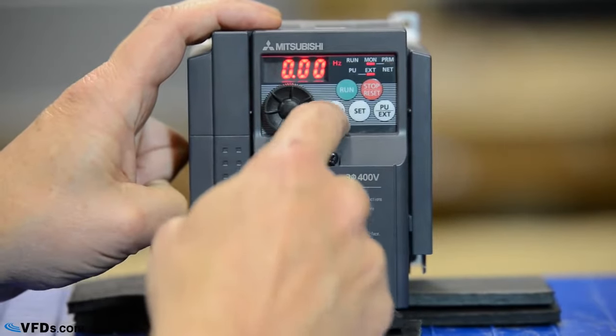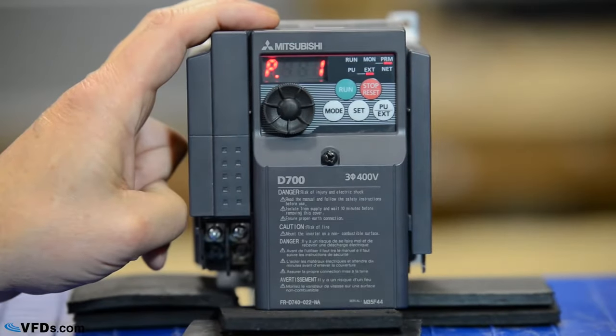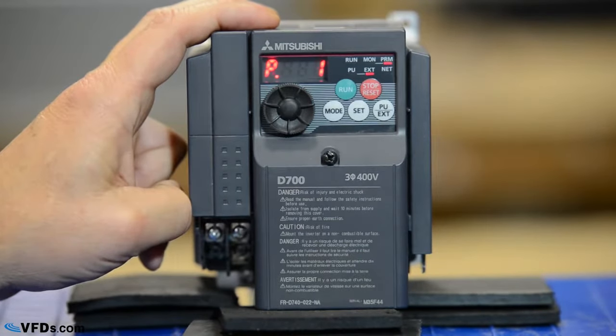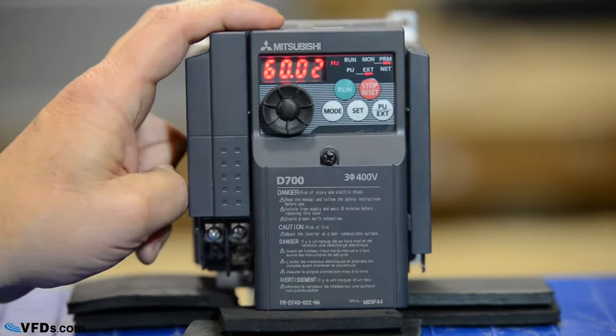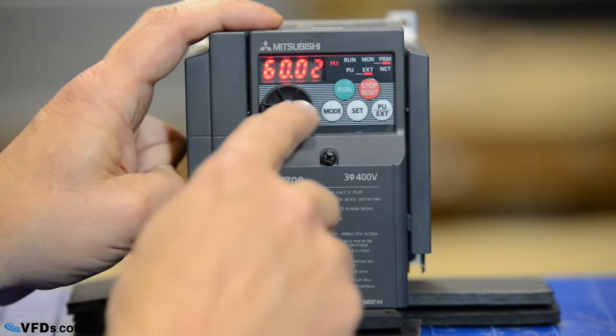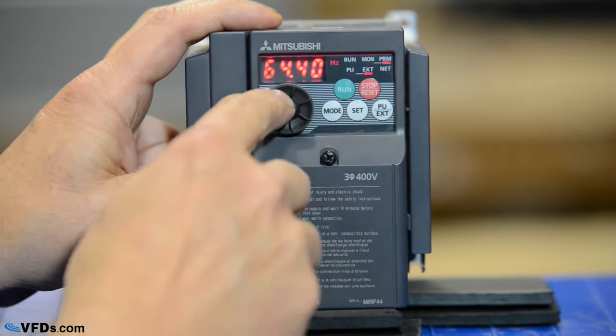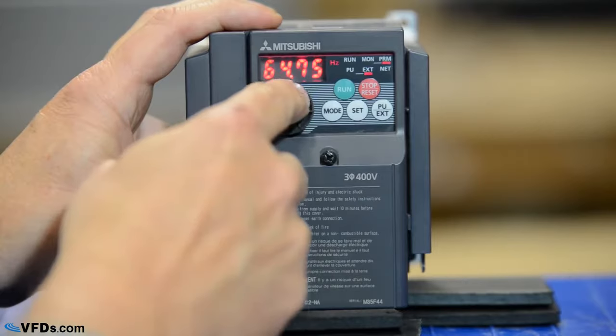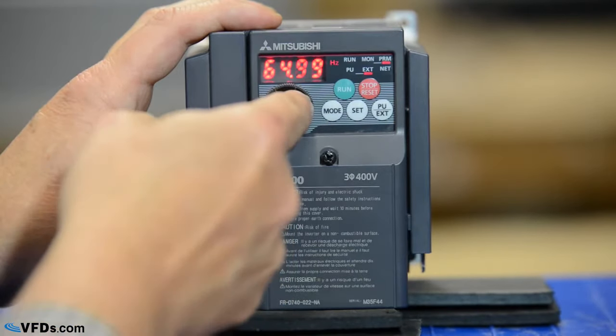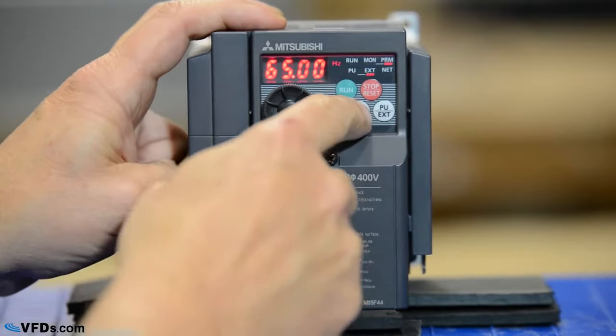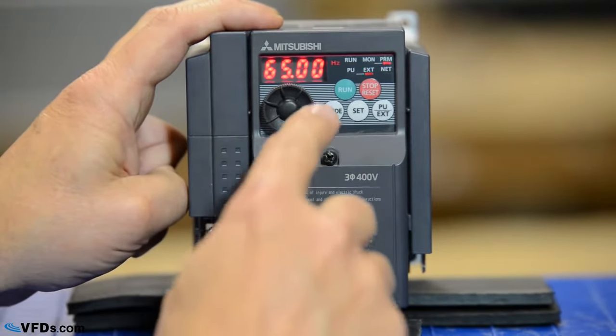Now if I go back to parameter mode, I'll start with parameter 1 and let's go through the first 10 parameters. Parameter 1 is my maximum frequency. I push set, it's set for 60.02 hertz. Maybe I'd like to allow this to go up to about 65 hertz. I'll change that to 65, and this wheel makes that very convenient. I push set and I'm now programmed for a maximum frequency of 65 hertz.